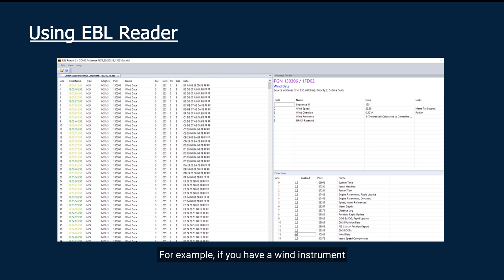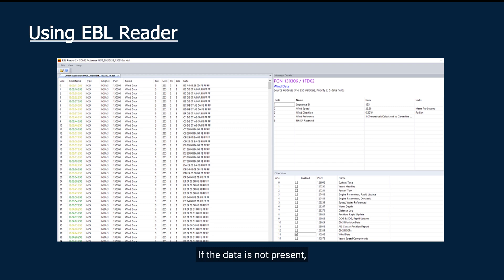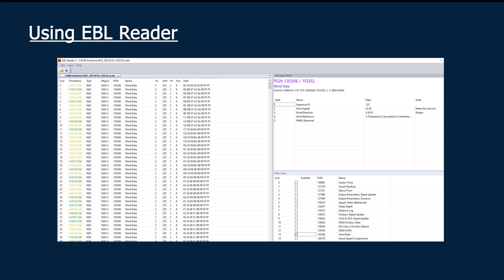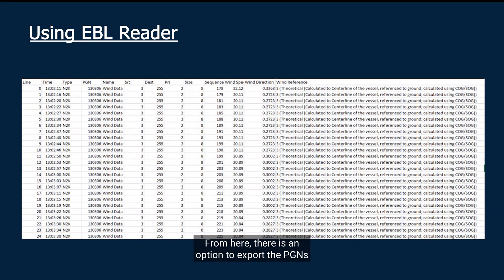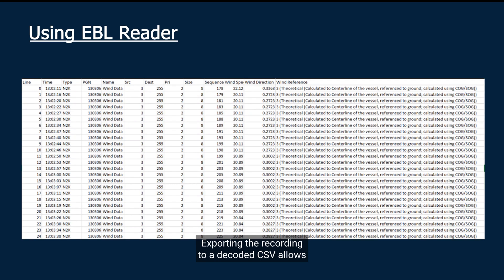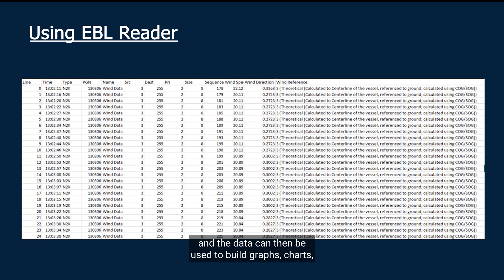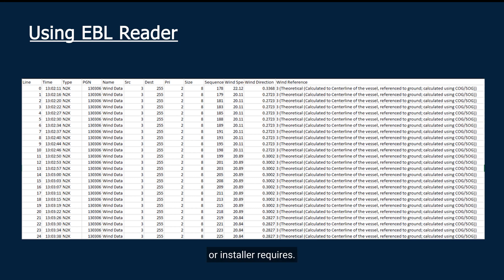For example, if you have a wind instrument on your network and your MFD stops receiving wind data, you can record this live in EBL Reader, then analyze the recording for wind data. If the data is not present, then you can determine that the wind instrument is not outputting PGNs. From here there is an option to export the PGNs to a CSV or decoded CSV. Exporting to a decoded CSV allows human-readable values to be seen in a program such as Excel, and the data can then be used to build graphs, charts, or any other data display the user or installer requires.